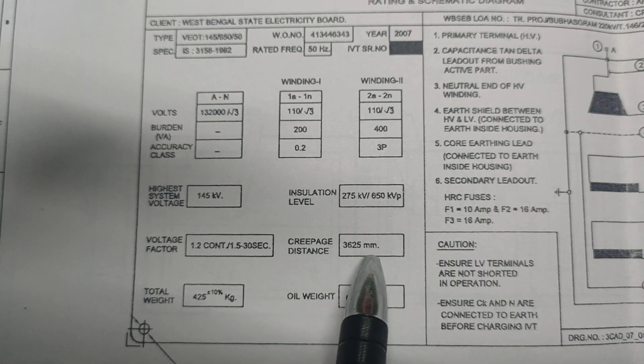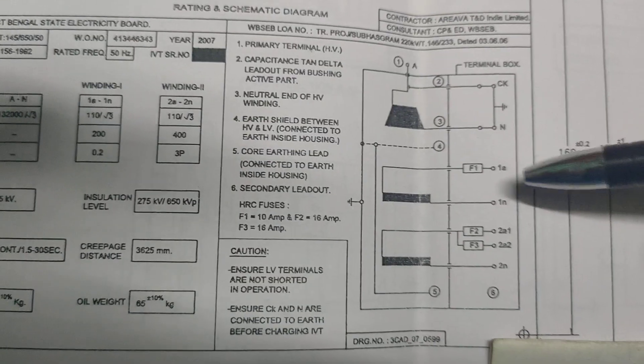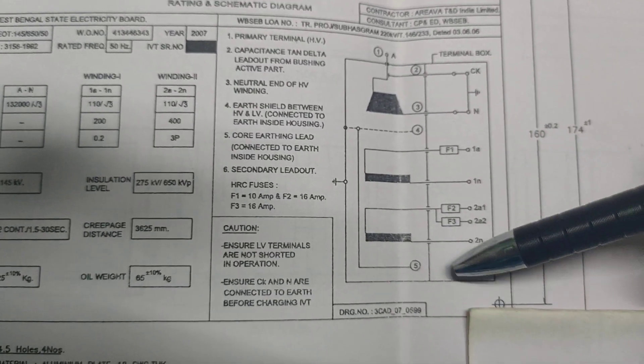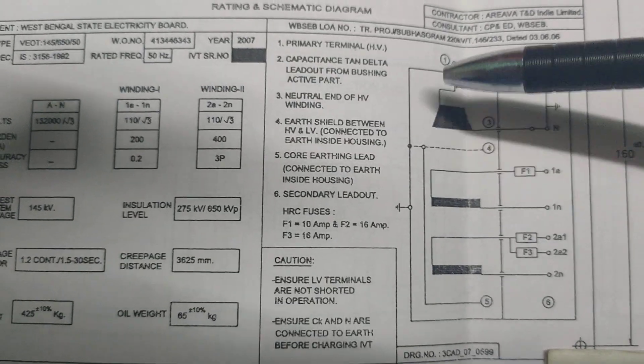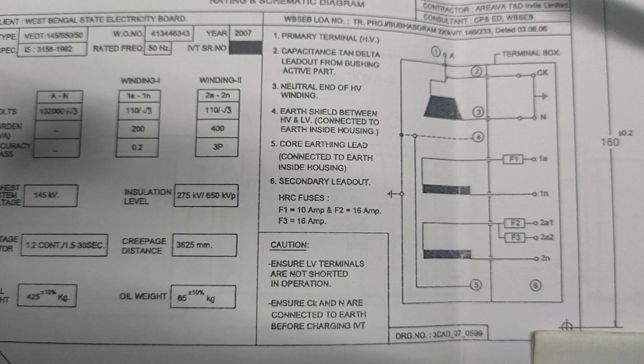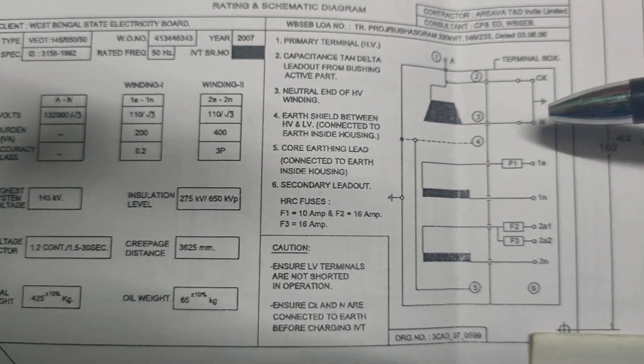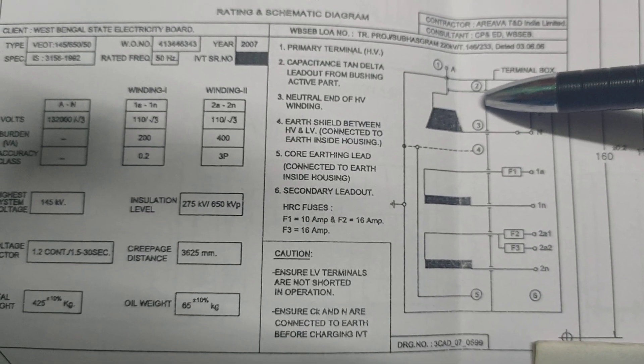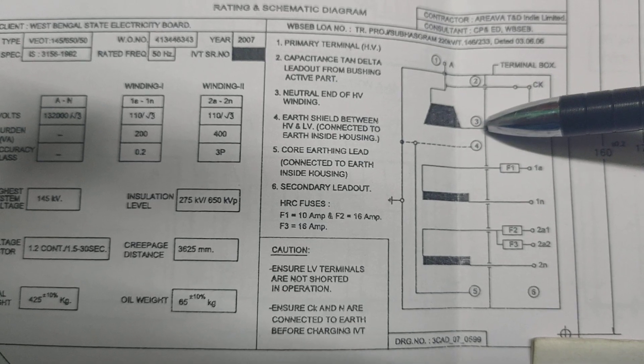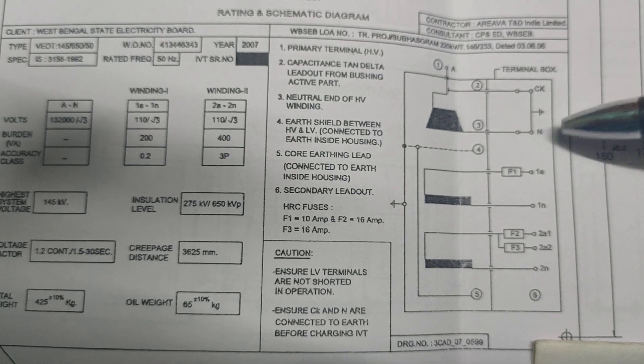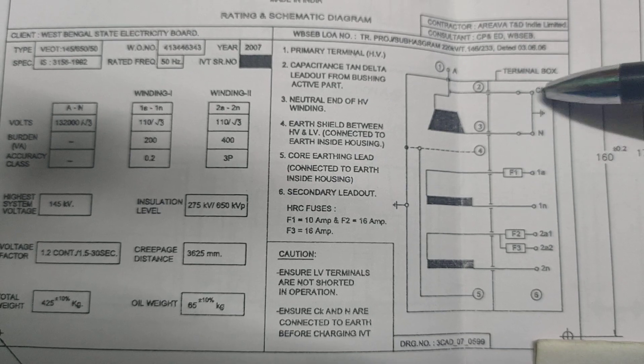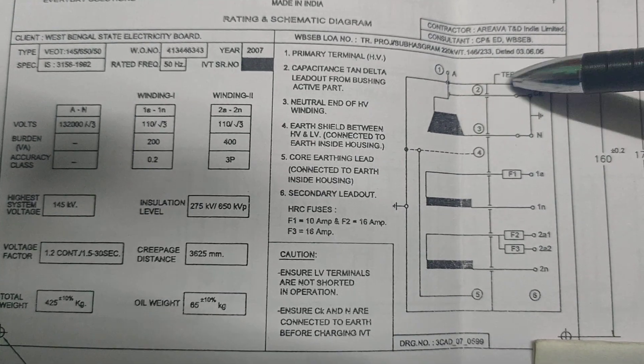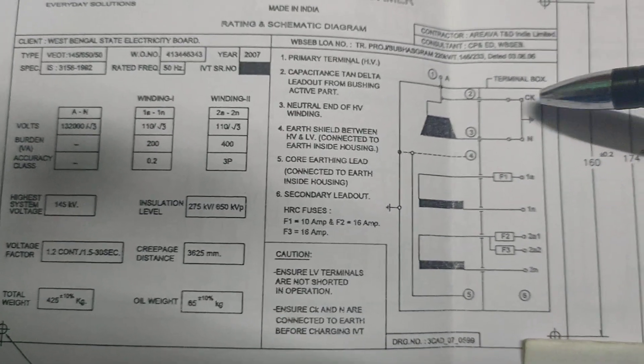This is the internal diagram, primary winding and secondary winding diagram of a potential transformer. So here 1 is the primary terminal HV, the start of the potential transformer. And 2 is the capacitance tan delta leadout from bushing active part. The 3 is the neutral end of the HV winding, Ck point. This is the tap delta point. Ck is the capacitance point or the tan delta point of the PT. So Ck and N should be shorted.